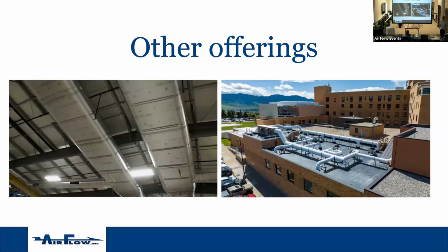I guess as a consulting engineer, if that's what I want to ensure the owner is provided, then the leakage testing is what needs to be addressed. Because at some point, the cost is going to be greater for the contractor to install their own spiral system versus the Thermaduct. No, we're almost always more expensive unless it's a higher R value, so R20 systems, we do really well at.